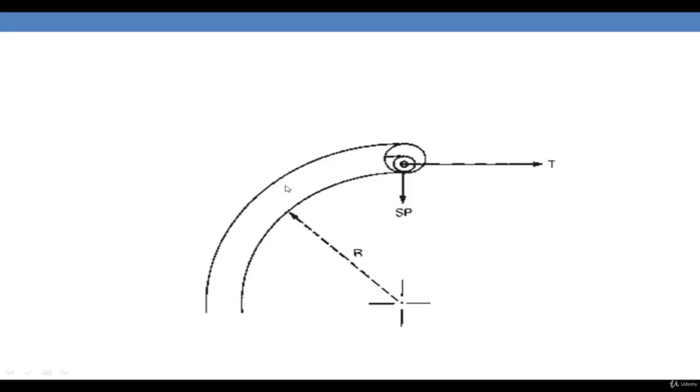If this pressure is greater than the rated value for this cable, then we would have the insulation damaged. Now we have all the basics of cable pulling calculations, and let us go to Etap to conduct a cable pulling calculation.